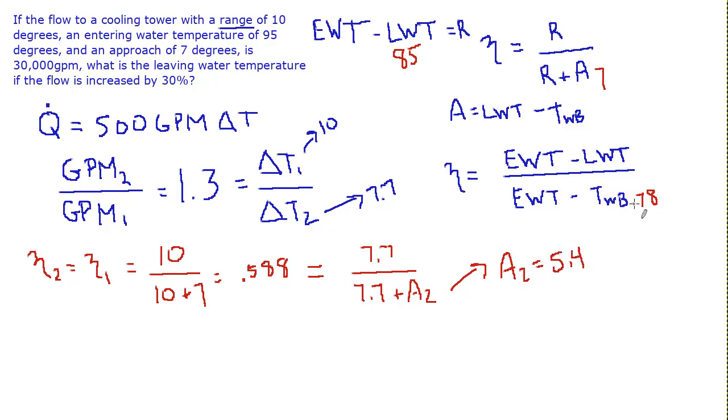And the wet bulb temperature hasn't changed. So we can use this formula and say that the approach is 5.4, which equals the leaving water temperature minus the wet bulb. So we add 78 to the other side, and the leaving water temperature equals 83.4.